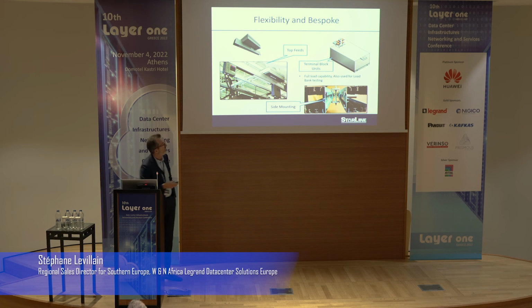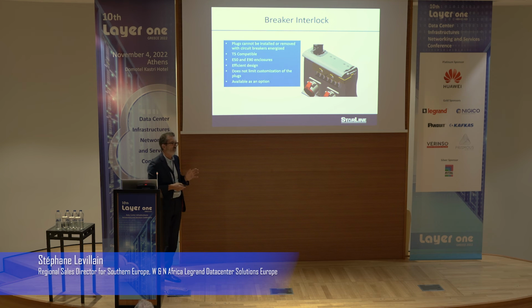In terms of flexibility, it's not all about the products, it's also about the testing. At the end of the day, you will need to test the full capacity of a data center to get the sign-off of the contractor, for instance, or your customer. So we have terminal block units. A terminal block unit is a big tap-off like this. You insert this tap-off at the end of the busway just to test all the power distribution up to the end of the busway. Then you have the cables going to the load bank and you can carry out your burn-in test, because usually in large colocation or on-premise hyperscale data centers, you need to carry out 2 hours, 3 hours, 4 hours burn-in testing, full load, to see if the data center is really robust. So with this kind of stuff, it's very important because it's very safe, and we will see some details.